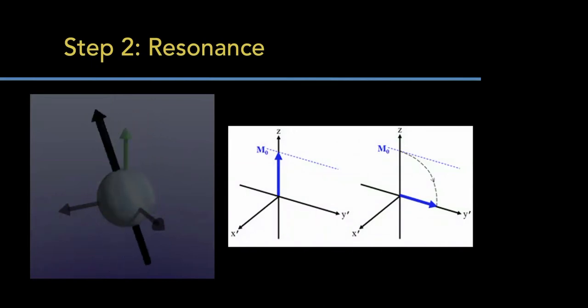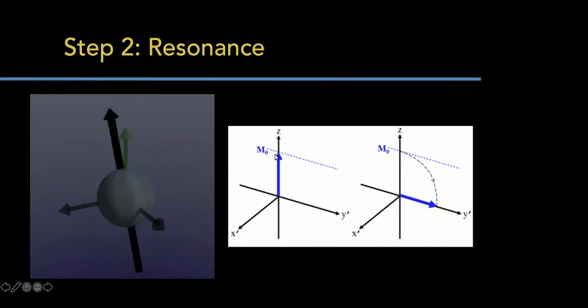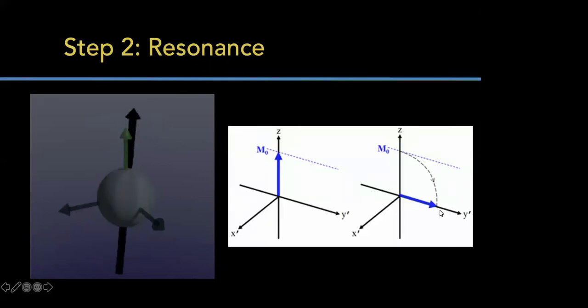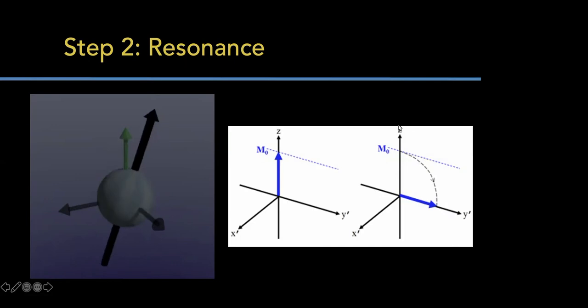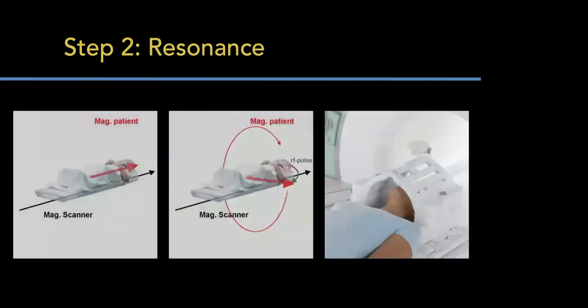The z-axis goes down the bore of the MRI. When the patient is at rest in the bore, the net hydrogen vector aligns along that z-axis. We apply a radiofrequency pulse matching the Larmor frequency, which knocks the magnetization perpendicular to the magnetic field. The protons start spinning around, wanting to return to their preferred position. We're essentially knocking them out of their energy-preferred state and then listening to what happens afterward. Coils placed outside the patient listen to those spinning energy vectors and gather the data.